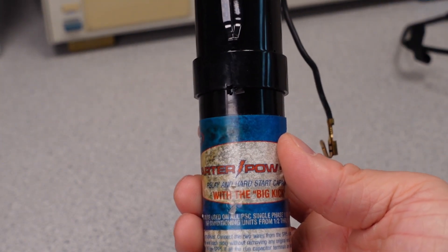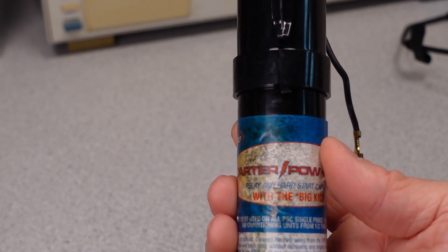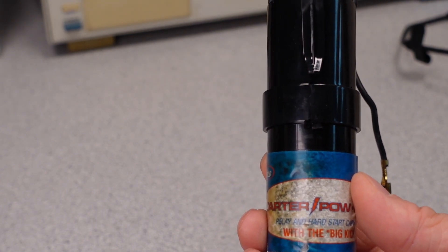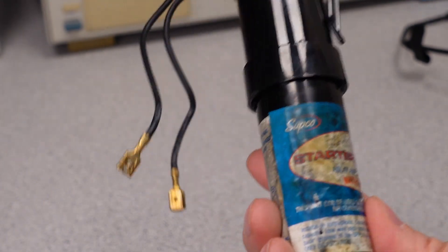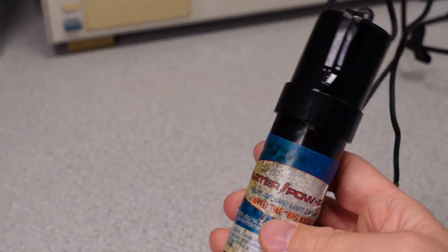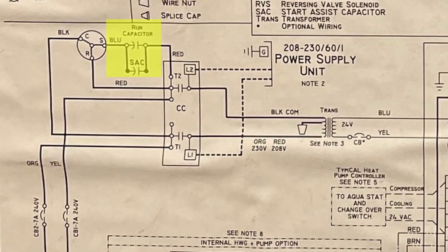And if it's not a problem with charge in the air conditioner, so you open it up, you see that there's no over pressure or under pressure warning light, there's a good chance that the problem has actually come from one of these. There are multiple capacitors in your unit and as they show on their little diagram right here, you have your run capacitor and your start capacitor.